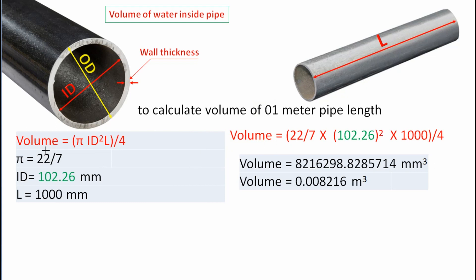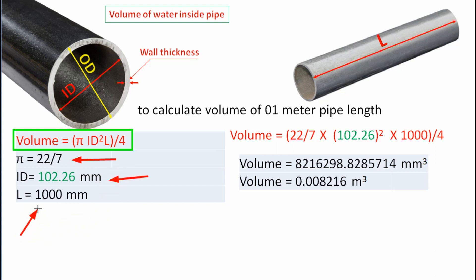To calculate the volume of water inside the pipe, we use the formula: volume equal to pi into pipe inside diameter squared into pipe length divided by 4. Pi is a constant with value 22/7. The pipe inside diameter is 102.26 mm and for our sample calculation, we assume pipe length equal to 1 meter or 1000 mm. Applying all values: volume = (22/7) × (102.26)² × 1000 / 4. After calculation, the volume of water inside the pipe for 1 meter length is equal to 0.008216 cubic meters.